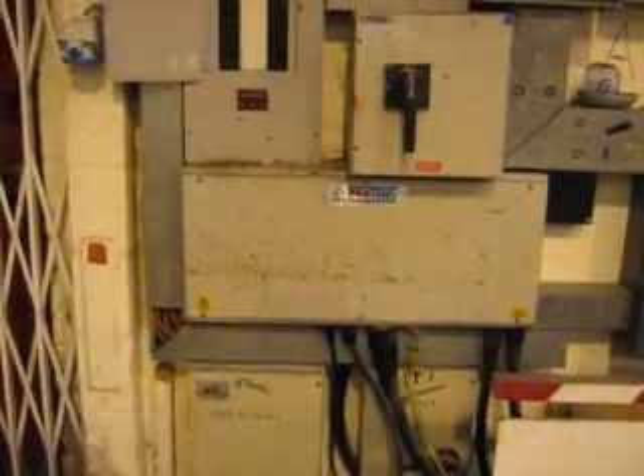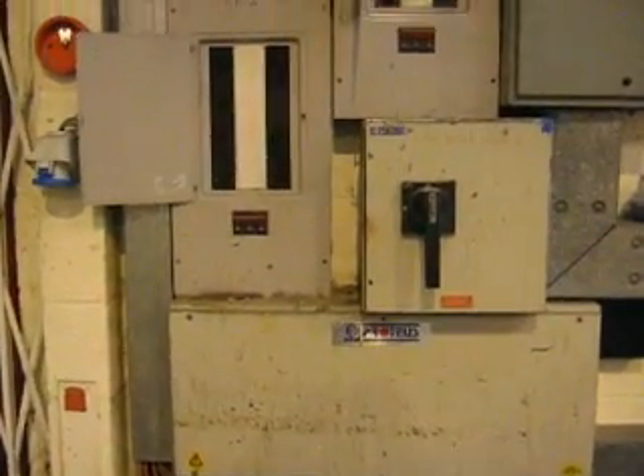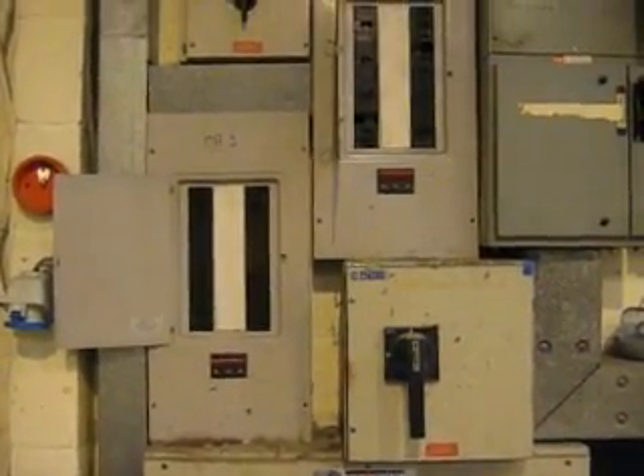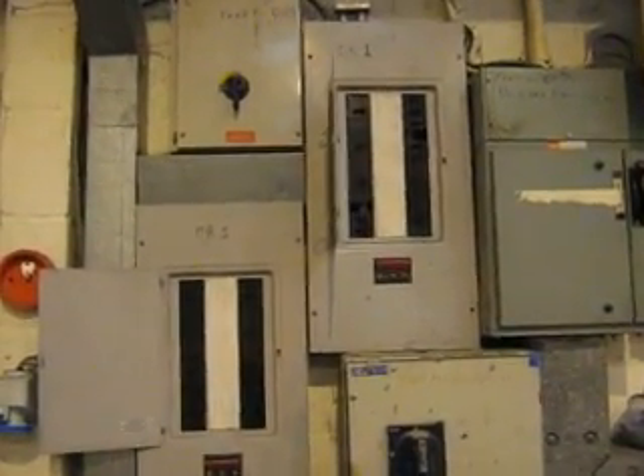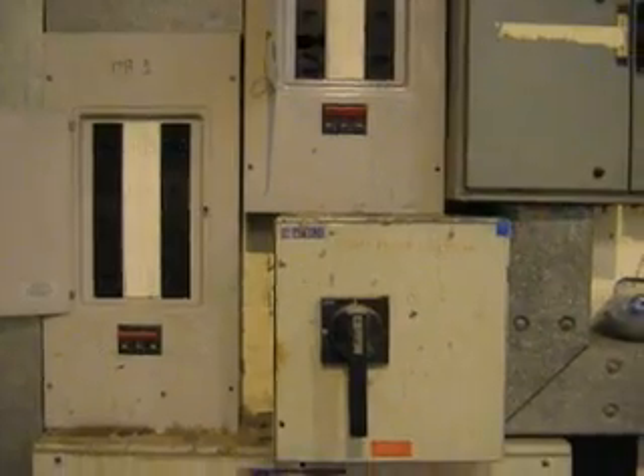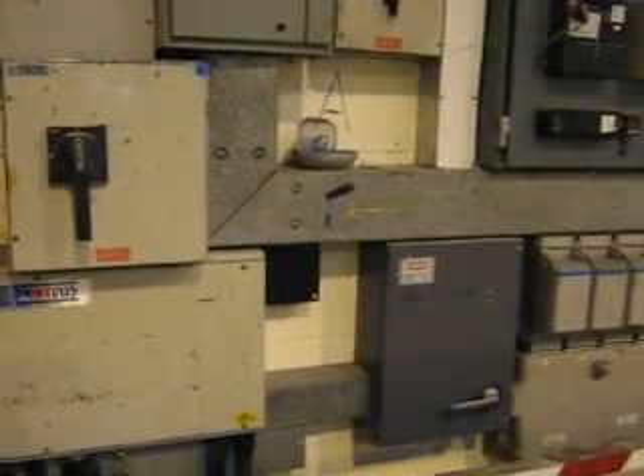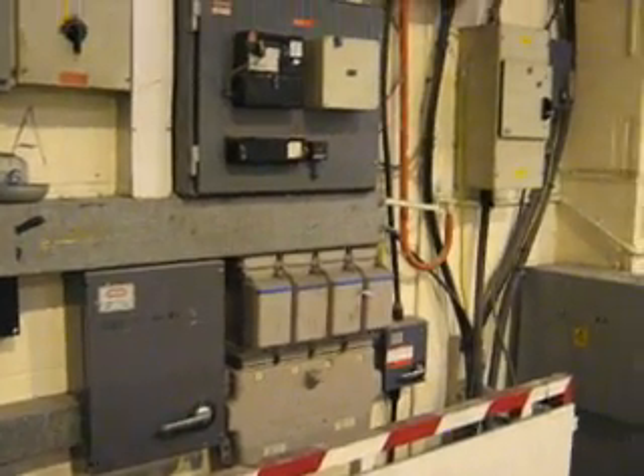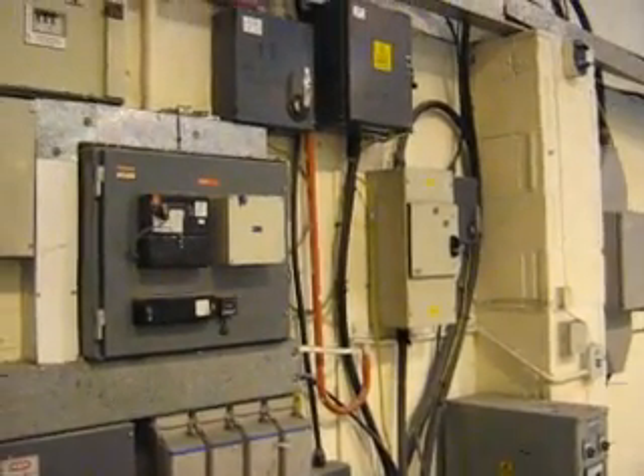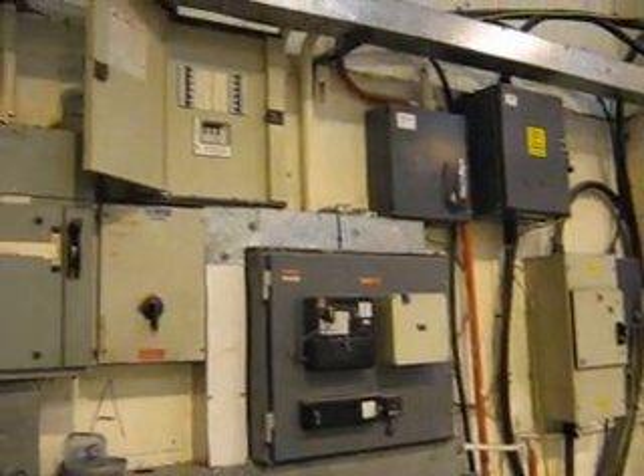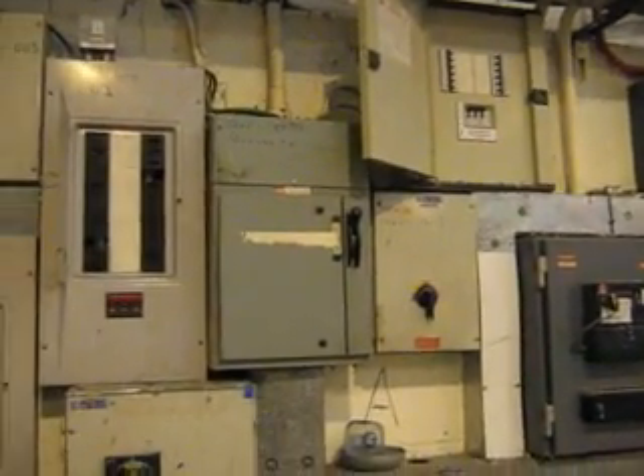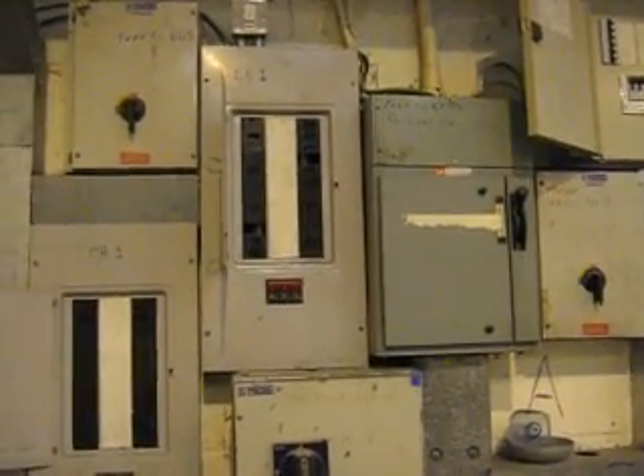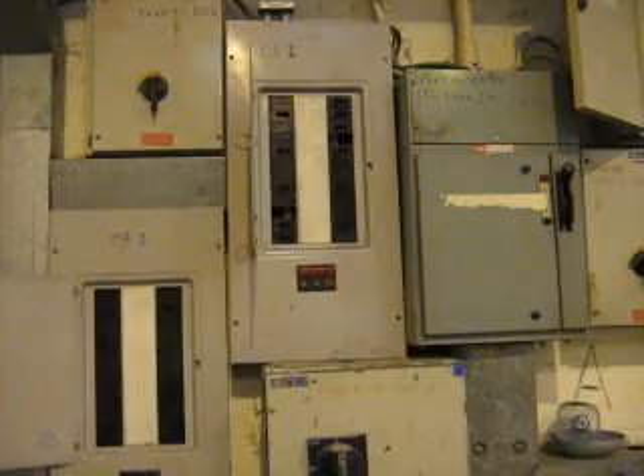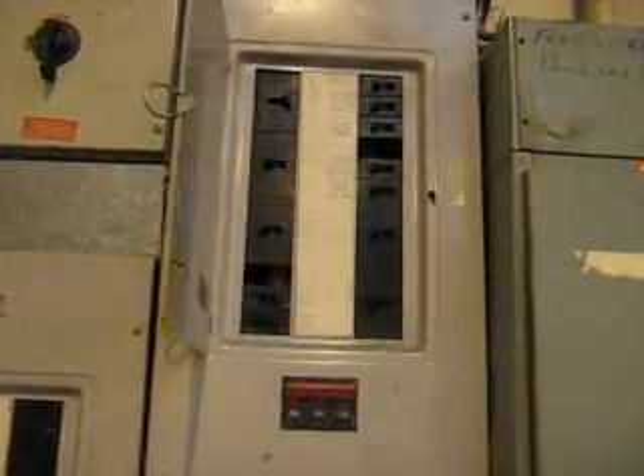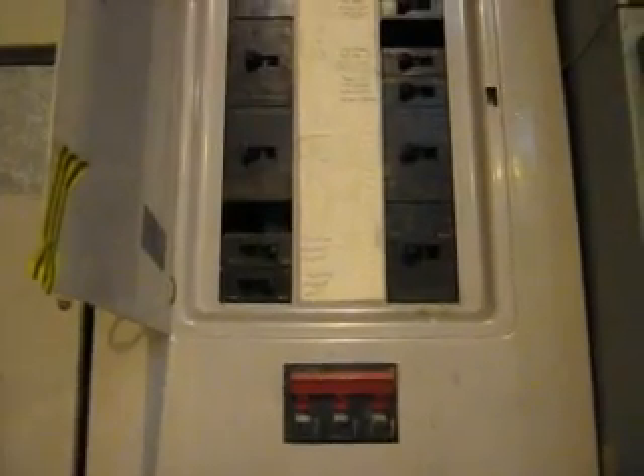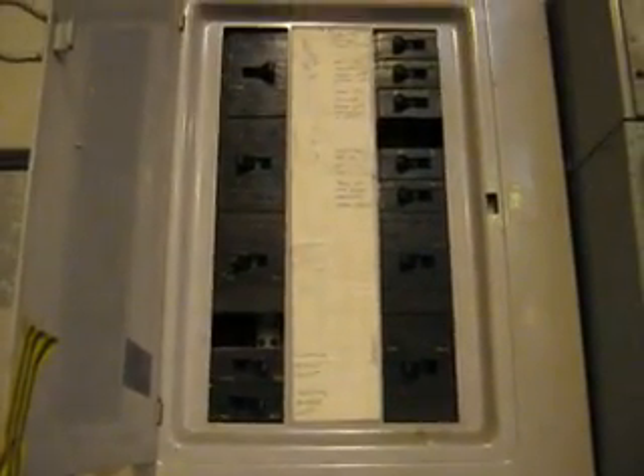This is an installation in an empty warehouse that is going to be refurbished, and my job is to compile a report on the existing installation, presumably with the purpose of retaining as much of it as possible and minimizing the cost of refurbishment. Much of the installation is dead. I've got to investigate why it's dead and see where it's dead for a very good reason.